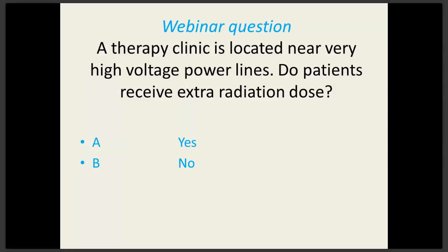There are lots of things to worry about in a therapy room besides the radiation, and I've listed a number of things that we are all exposed to in the course of a working day. There's radio frequency from the klystron and the magnetrons. There's electromotive force from the high voltage. Ozone is produced when the machine is producing radiation, say during testing or the commissioning phase, when it's running for literally hours. There is a small amount of ozone, O3, produced in the room by the ionizing radiation. That is an occupational hazard.